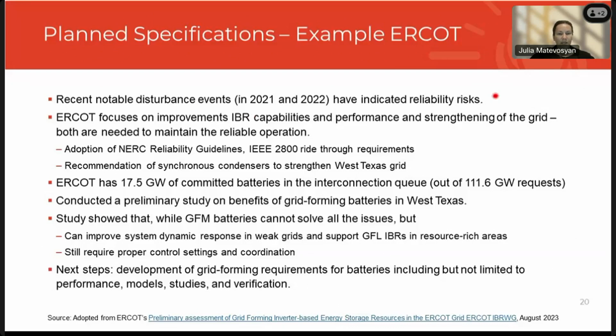So 2 of these events happened in Texas, within a year from each other. After that, ERCOT strongly focuses on improvement of inverter-based resource capabilities and performance, but also on trying to strengthen the grid in this area, because both events happened in a weak grid area and propagated across very large distances, far away from the fault. And that's exactly because in this weak grid area, voltage drop propagates a big distance.